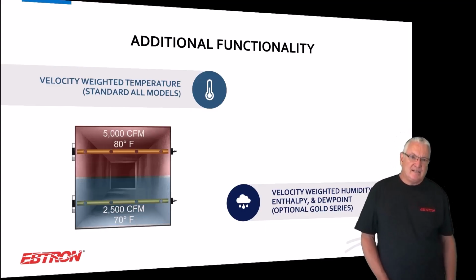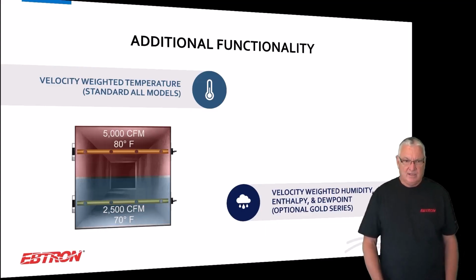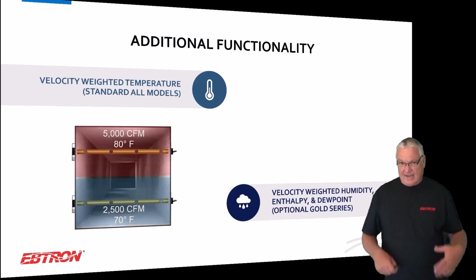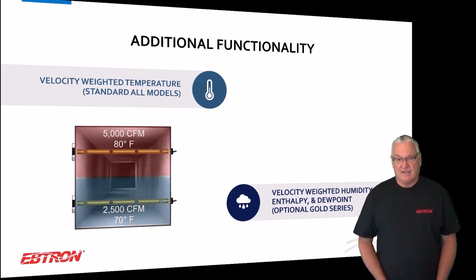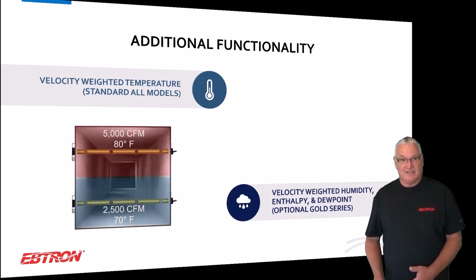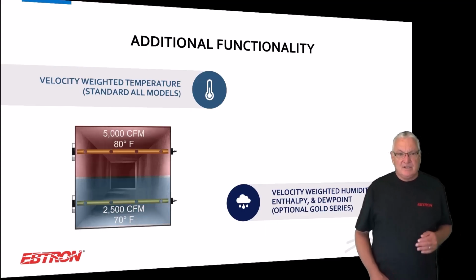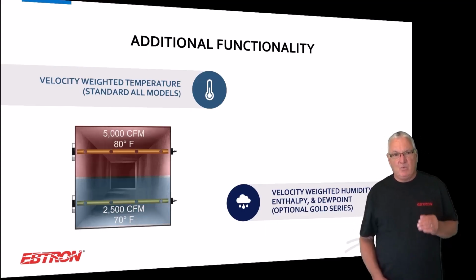Additional functionality, things that you don't use, that you should be using, okay? All of our devices come with velocity weighted temperature, except for one model of our X1000-T, because it only has one analog output, the A1000-T, and it just has airflow. But every other device has airflow and temperature standard. But it's not just temperature, it's velocity weighted temperature.